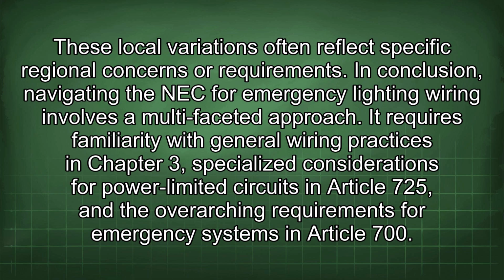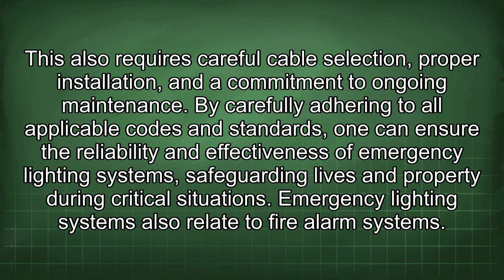In conclusion, navigating the NEC for emergency lighting wiring involves a multifaceted approach. It requires familiarity with general wiring practices in Chapter 3, specialized considerations for power-limited circuits in Article 725, and the overarching requirements for emergency systems in Article 700. This also requires careful cable selection, proper installation, and a commitment to ongoing maintenance. By carefully adhering to all applicable codes and standards, one can ensure the reliability and effectiveness of emergency lighting systems, safeguarding lives and property during critical situations.